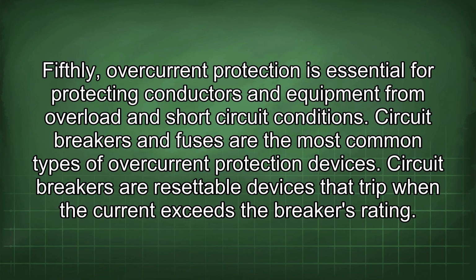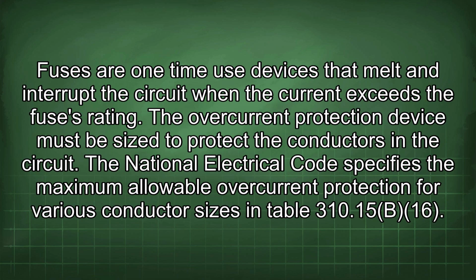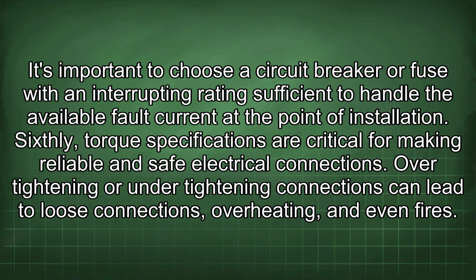Circuit breakers are resettable devices that trip when the current exceeds the breaker's rating. Fuses are one-time use devices that melt and interrupt the circuit when the current exceeds the fuse's rating. The overcurrent protection device must be sized to protect the conductors in the circuit. The National Electrical Code specifies the maximum allowable overcurrent protection for various conductor sizes in Table 310.15(B)(16). It's important to choose a circuit breaker or fuse with an interrupting rating sufficient to handle the available fault current at the point of installation.